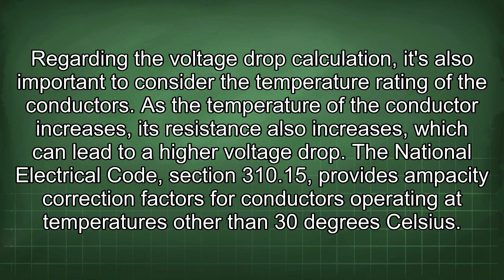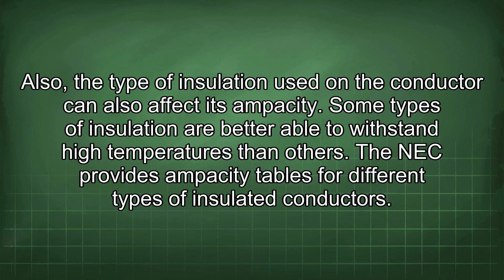Also, the type of insulation used in the conductor can also affect its ampacity. Some types of insulation are better able to withstand high temperatures than others. The NEC provides ampacity tables for different types of insulated conductors.